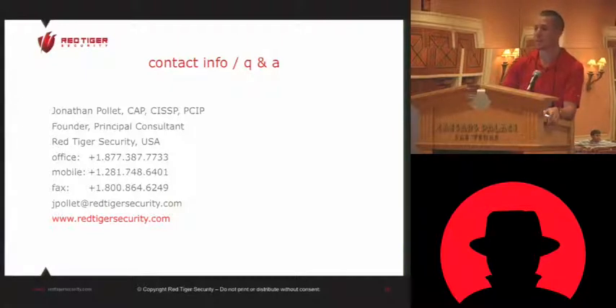That's right, exactly. In fact, I think in 2005 we wrote a white paper, 6 ways to protect the perimeter. And we put in that one-way diode, push a secure file onto a server and let someone else pick it up. We even went down the road of building a prototype for a system that only transferred data serially. The data was collected from the SCADA system, and then there was a serial RS-232 cable from that device to another server, and it pushed the data over a serial connection. So you can't even hack backwards. It won't propagate through because it's a non-routable protocol. We produced that as a proof of concept as well.